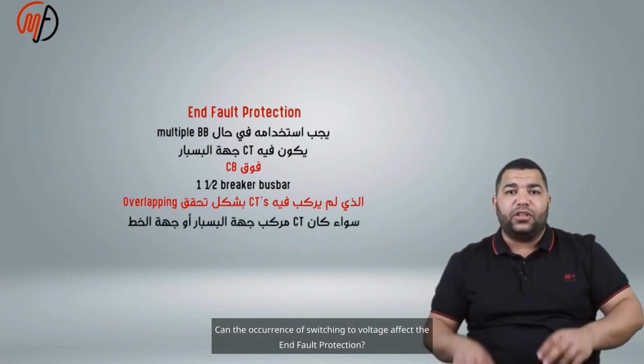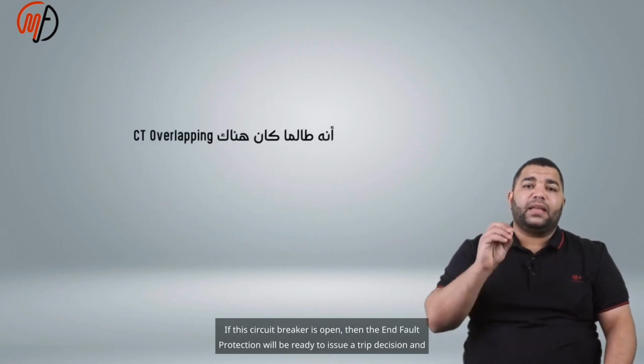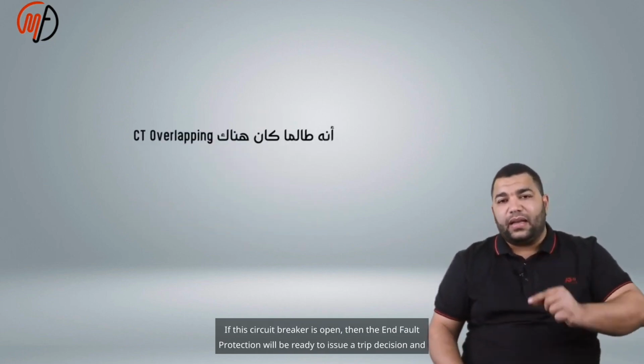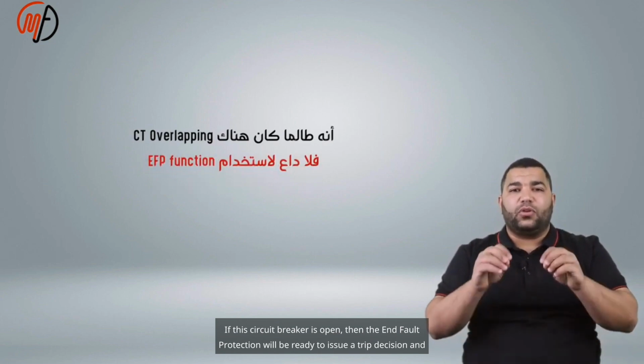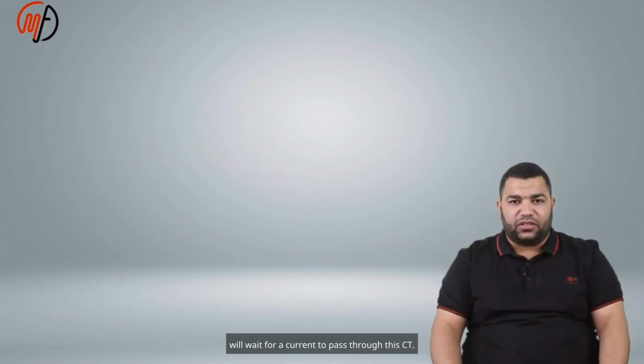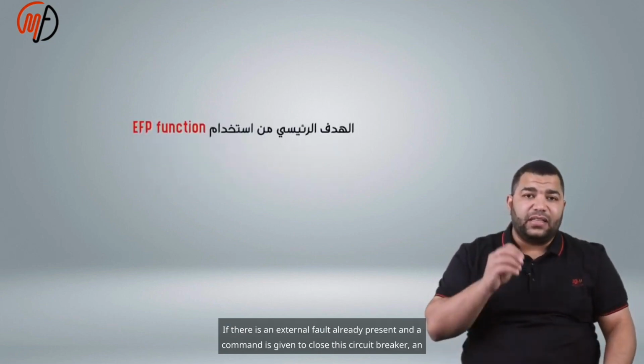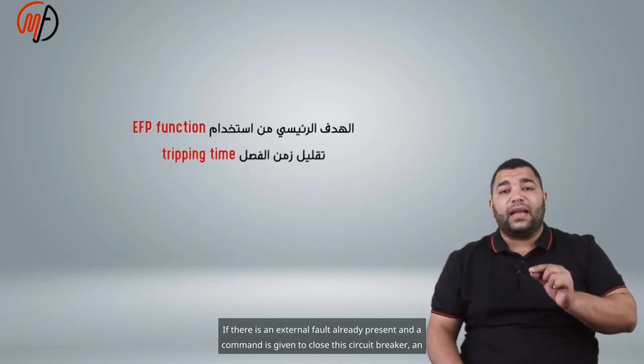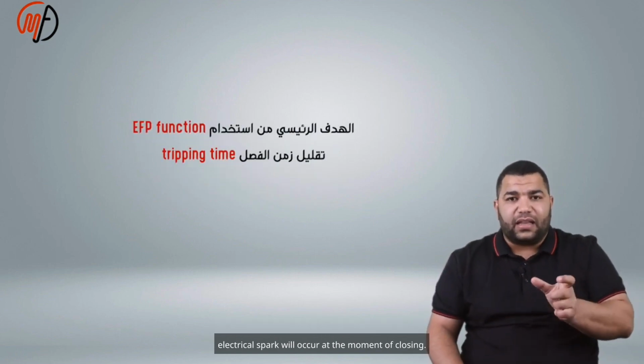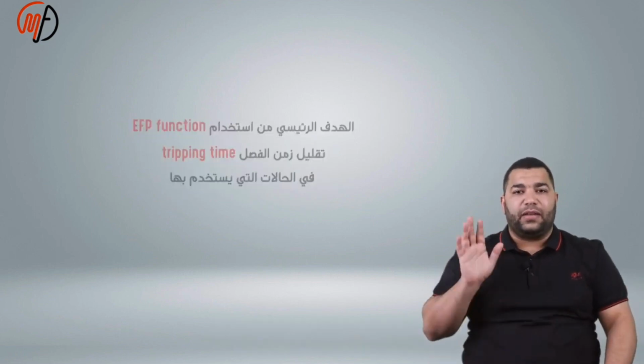Can the occurrence of switching onto a fault affect the end fault protection? Assume the CT is installed on the bus bar side. If this circuit breaker is open, then the end fault protection will be ready to issue a trip decision and will wait for a current to pass through this CT. If there is an external fault already present and a command is given to close this circuit breaker, an electrical spark will occur at the moment of closing.